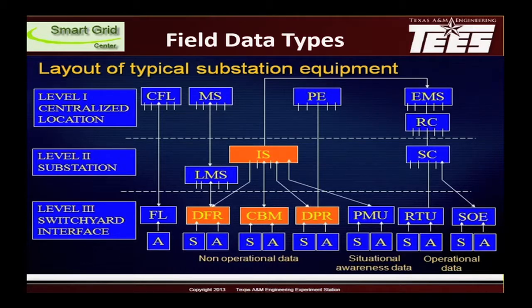I think I made a point with this. The only thing I want to bring to your attention is an important point, written down at the bottom. In power systems, we have terminology: operational data for SCADA data, supervisory control and data acquisition data. That means operators are using that data to run the system. Non-operational data from relays and recorders is triggered data—when an event occurs, the device triggers. That data is not used for operating purposes. However, if processed in real time and passed on and integrated with the operational data, it can bring value, and it can be done.